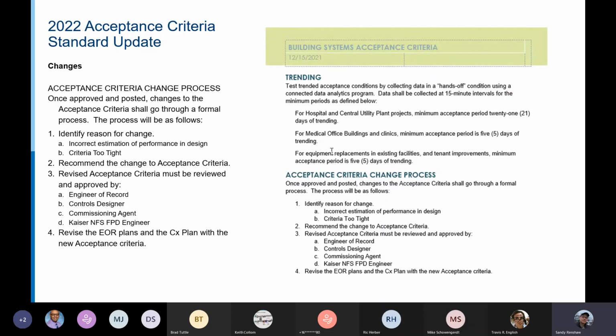We've also instituted an acceptance criteria change process. So once approved and posted, changes for the acceptance criteria will go through a formal process, just like you were doing a change order to the project. We would expect to identify a reason for the change. As we said before, it could be an incorrect estimation of the performance in design, criteria too tight, maybe criteria too loose. The recommended change. The revised acceptance criteria must be reviewed and approved by the engineer of record, controls designer, commissioning agent, and the Kaiser NFS planning and design engineer. And then once approved, you would revise the engineer of record's plans or specifications with the new criteria and update the commissioning plan.